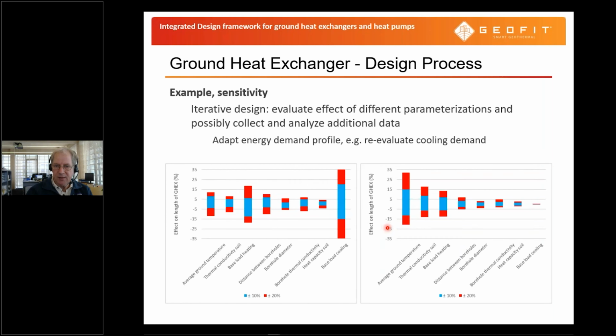Another example of sensitivity is to look at the effect of different parameters. For instance, the average ground temperature, thermal conductivity of the soil, the base load heating, distance between boreholes, etc. Then we can change a parameter by a certain percentage, for instance 10 or 20%, and look at the effect on the length of the ground heat exchanger that is required. In this example, we see that the base load for cooling has a very high effect. That means that if we could achieve a better balance between heating and cooling load, we would get a smaller heat exchanger, but also a more robust design.